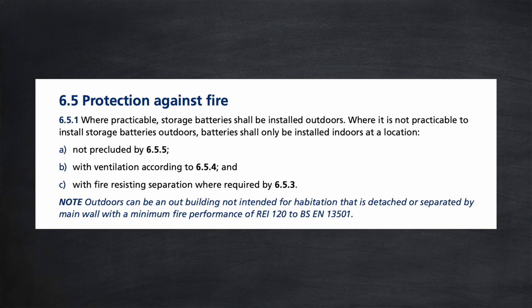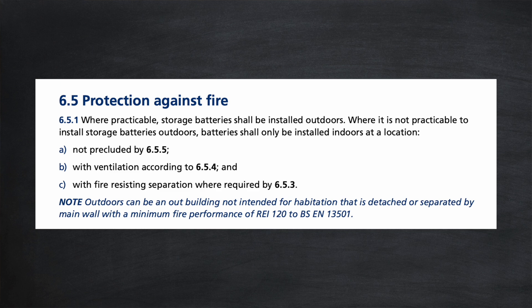Let's have a read. Section 6.5 is the pertinent section: protection against fire. 6.5.1 — where practicable, storage batteries shall be installed outdoors. So the guidance is stating right off the bat that home batteries should ideally be installed outdoors if possible. And where it is not practicable to install storage batteries outdoors, batteries shall only be installed indoors at a location not precluded by section 6.5.5.